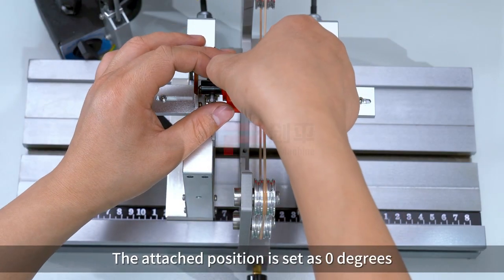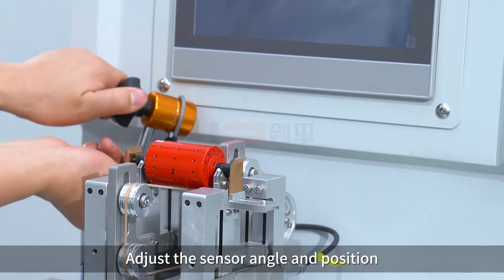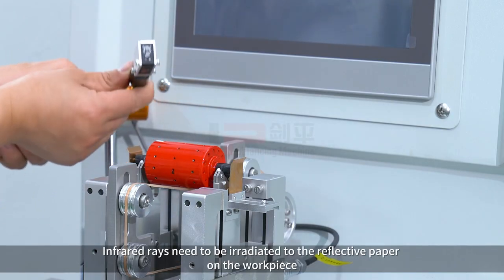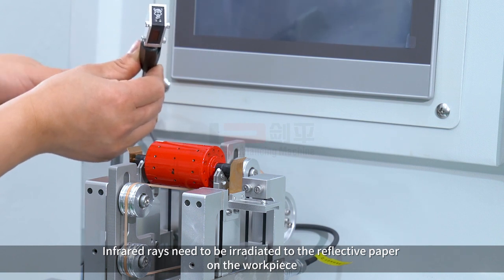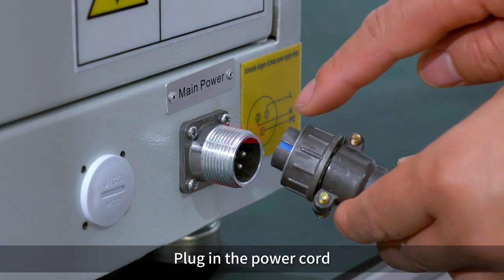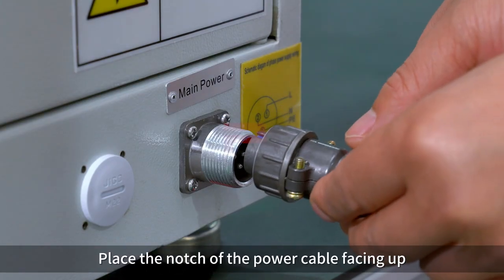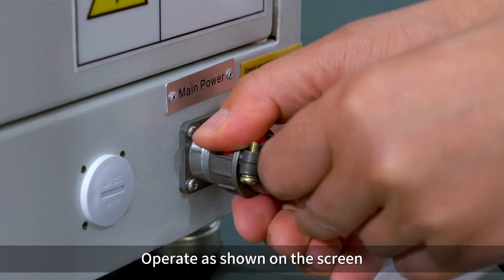Attach reflective paper to the workpiece — the attached position is set as 0 degrees. Adjust the sensor angle and position so that infrared rays are irradiated onto the reflective paper on the workpiece. Lock the knob, then plug in the power cord with the notch of the power cable facing up, as shown on the screen.